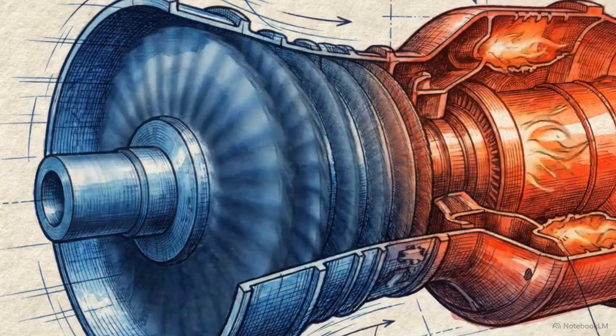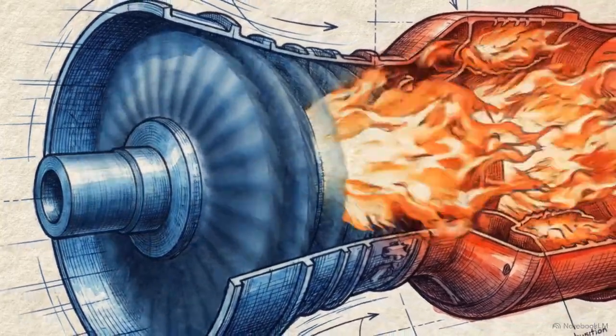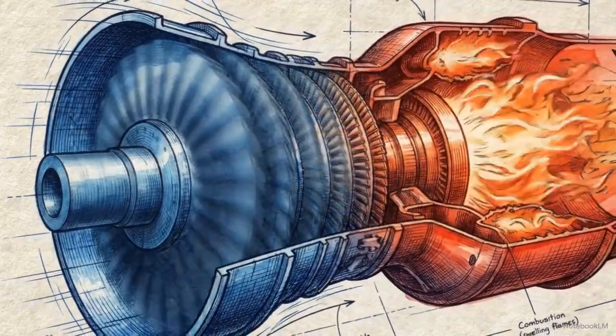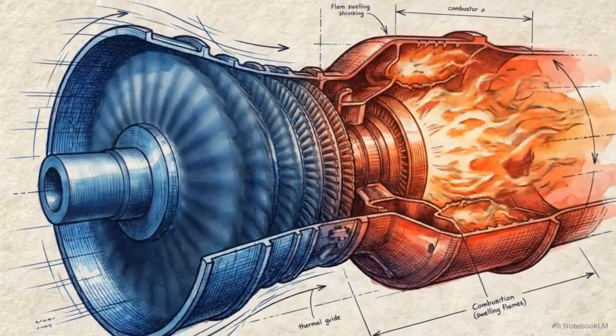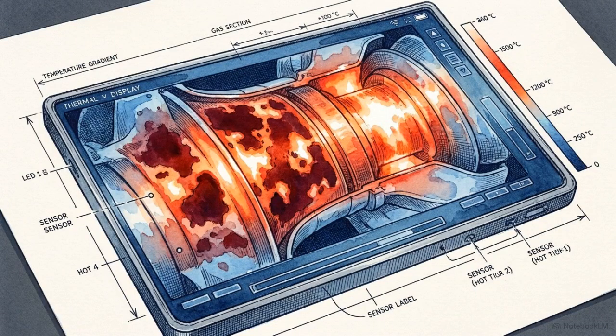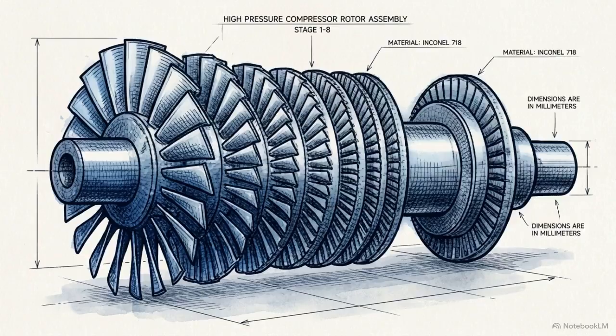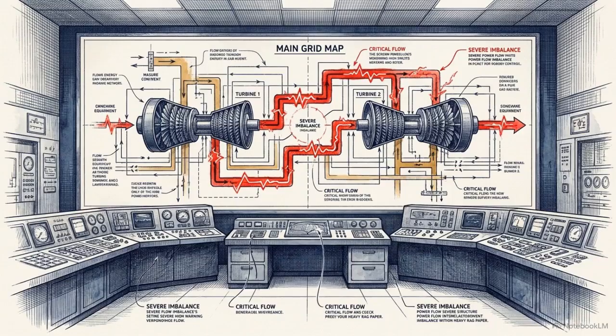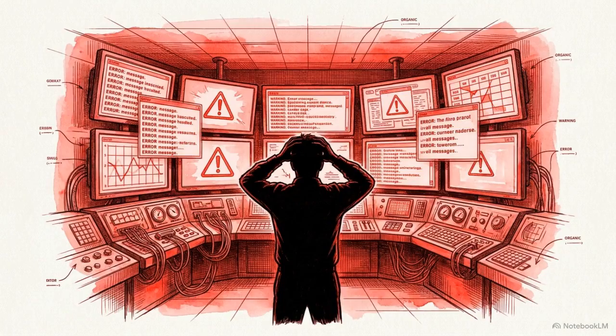Inside the engine enclosures, this inflicts severe mechanical stress on the turbine architecture. The gas generator core is forced to rapidly surge and choke, causing extreme thermal load fluctuations across the hot section. The turbines themselves are not broken. The root cause of this violent oscillation is a flaw in how the control logic has been applied to a shared system. Instructing two advanced machines to independently act as absolute frequency anchors guarantees instability. By demanding tighter individual control from each unit, the operators create total system chaos.